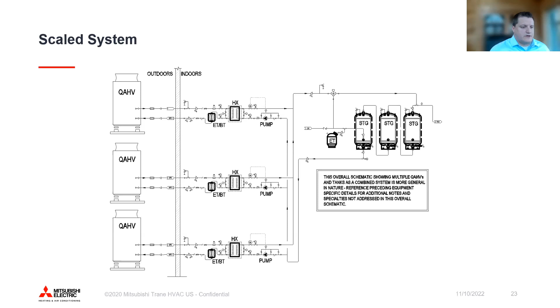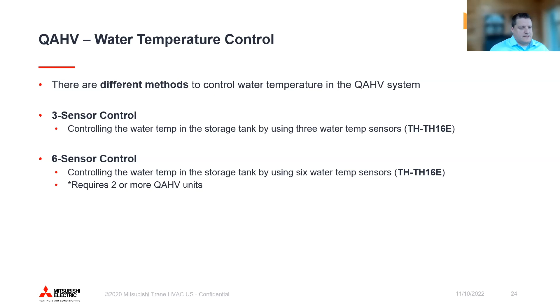So how do we control the heat pump? Right now, this is done off of a few different ways, but mainly it's controlled on sensors in those storage tanks. So right now you have two methods, essentially, a 3-sensor control or 6-sensor control. And for the most part, you're always turning on the system at one sensor and turning it back off at the other sensor.